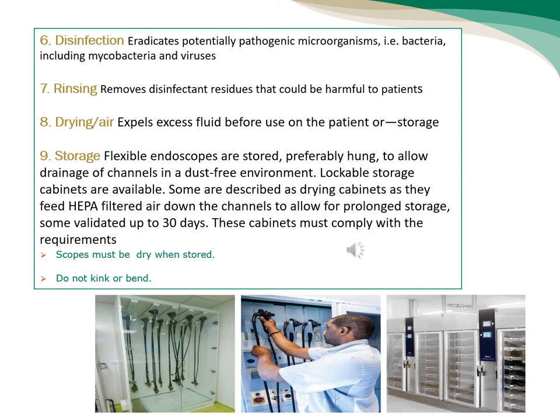Disinfection: eradicate potentially pathogenic microorganisms, for example bacteria including mycobacteria and viruses. Rinsing removes disinfectant residue that could be harmful to the patient. Drying by air expels excess fluid before use on the patient or storage. Flexible endoscopes are stored preferably hung to allow drying of channels in a dust-free environment. Lockable storage cabinets, some described as drying cabinets, feed HEPA-filtered air down the channels.